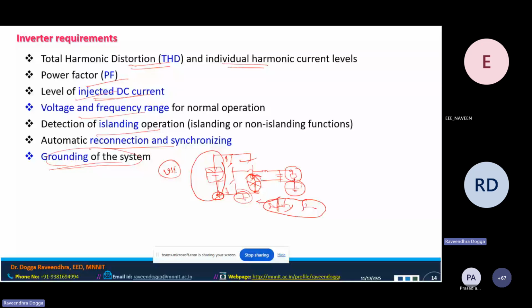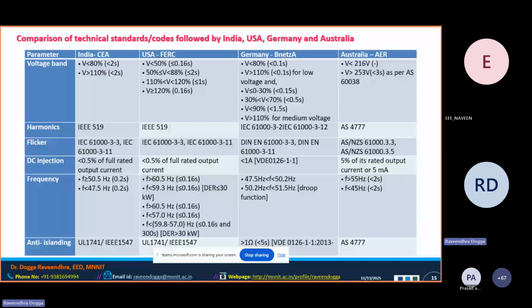A lot of countries follow different kinds of standards. I'm not going too deep, but everyone should know the requirements before going to the design of power conditioning units, meaning photovoltaic inverters. So what is the voltage range, what is the harmonics, what is the standard DC offset injection? In India, we follow less than 0.5% of the full rated current; there should not be more than this, otherwise your inverter design will not be accepted. This is also the frequency range, and we follow the anti-islanding IEEE standard.